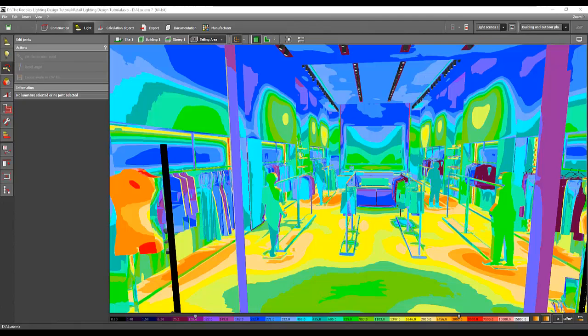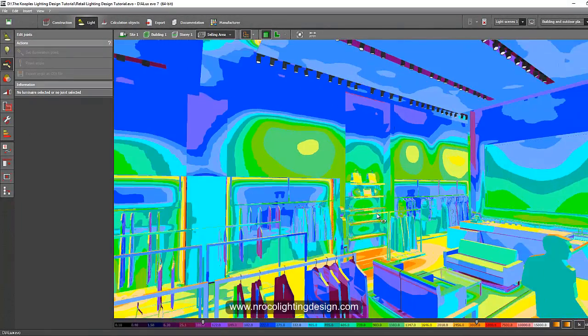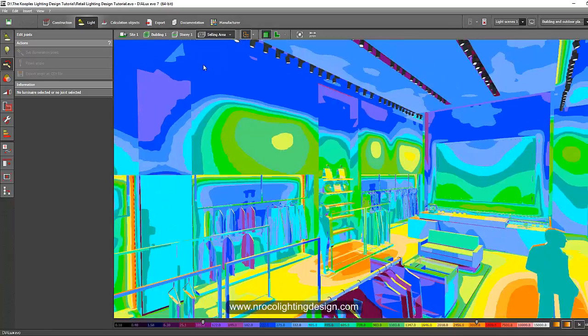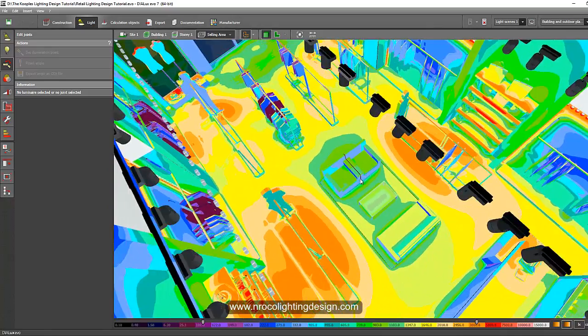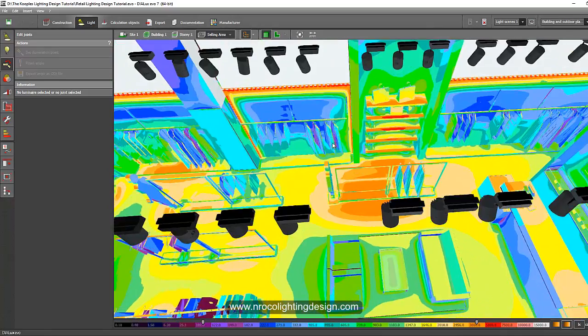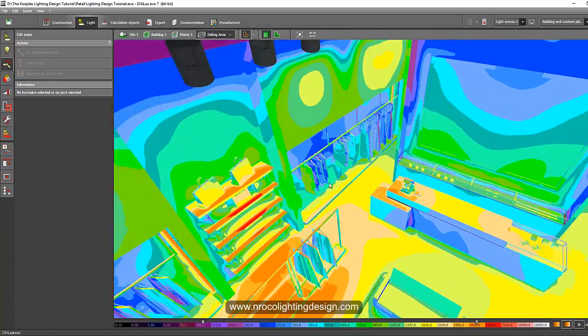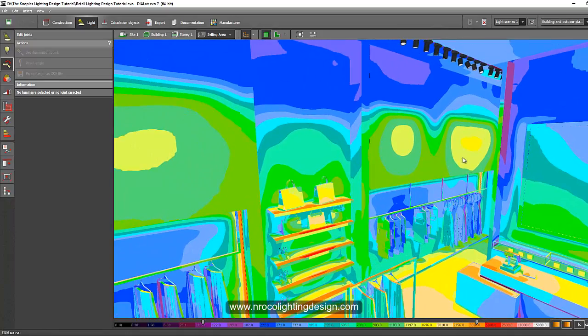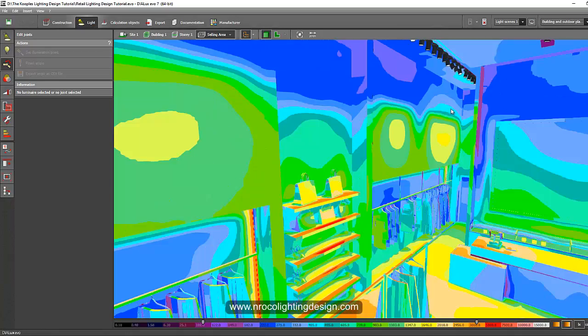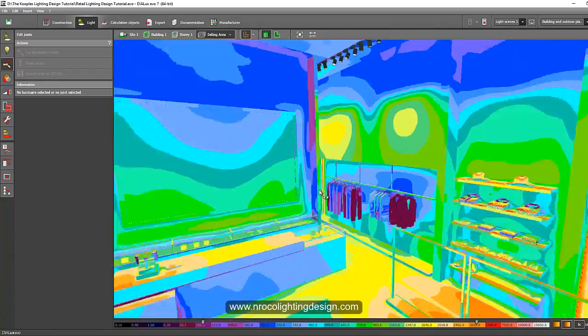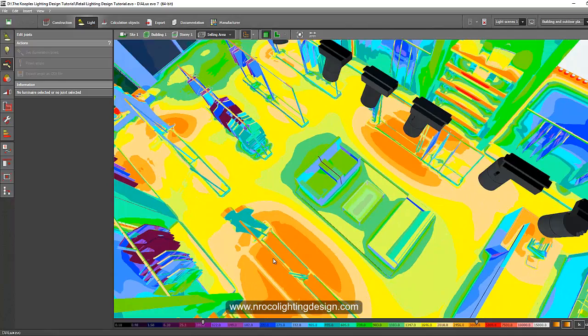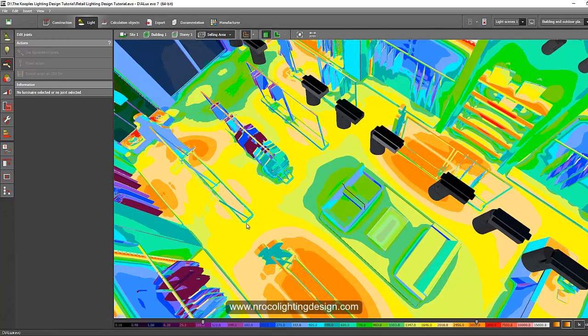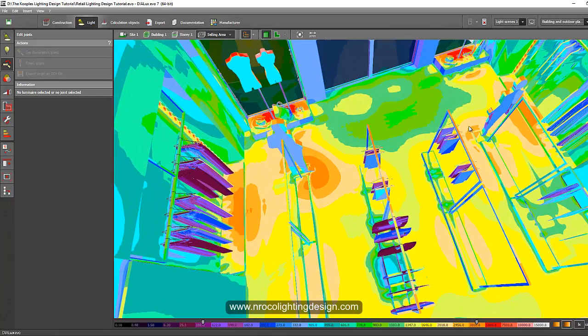Good afternoon everybody, this is Nelka again. Let's continue our retail lighting design tutorial. The topic now is how to aim spotlights. I ran another calculation and aimed some of the spotlights already. This is the overall evaluation - I focused all the spotlights on the merchandise on the racks and the shelves are brighter now.